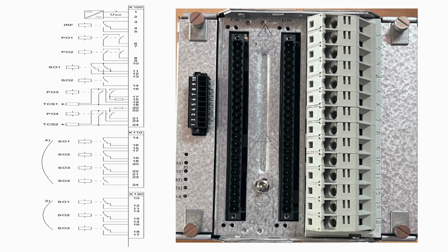After that you can see here PO1, SO1. PO1 is a power output, SO1 is a signal output. So in RET 615 you will get two different outputs, PO1 power output and SO1 signal output. Power output is a high duty contact, and this contact is capable of high currents because our protection relay will connect to the master relay 86 or the circuit breaker tripping coil.